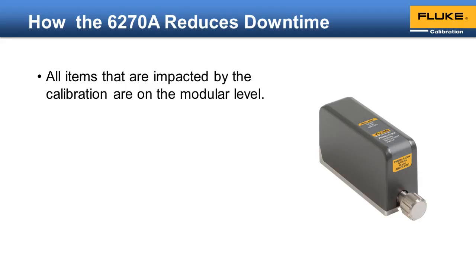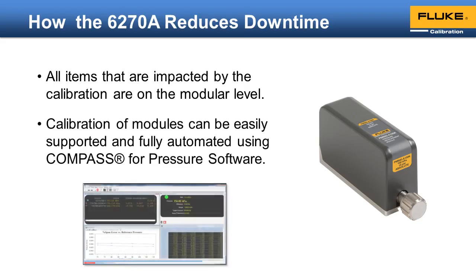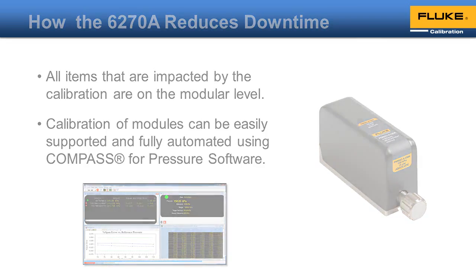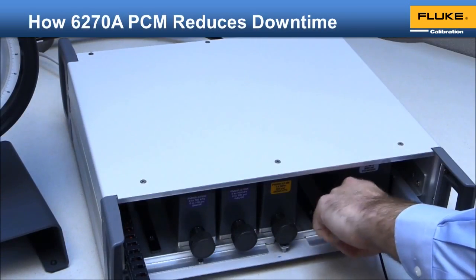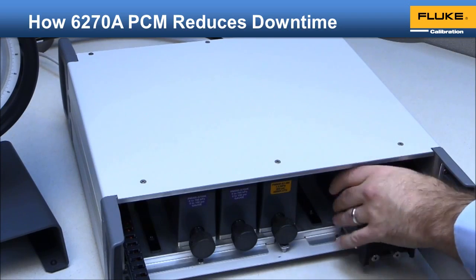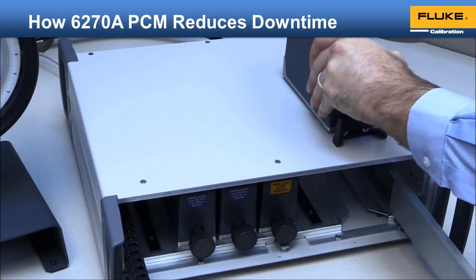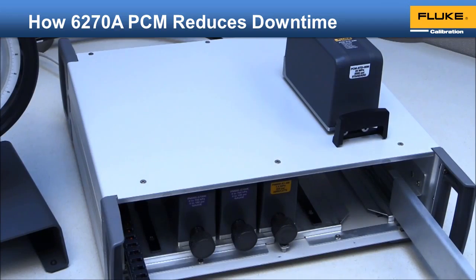All external influences that can affect the output of the pressure sensor were taken into account in the design to ensure that it performs the same, whether installed in a 6270A chassis or being calibrated using the optional calibration kit. This includes things like temperature, supply voltage, and EMC. Calibration of the modules is made quick and easy with the Compass for Pressure software. The control functionality in the 6270A is also encapsulated in a module. The pressure control module, or PCM, can also be easily removed and replaced through the front panel for easy troubleshooting and repair.